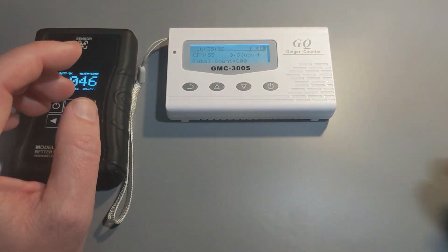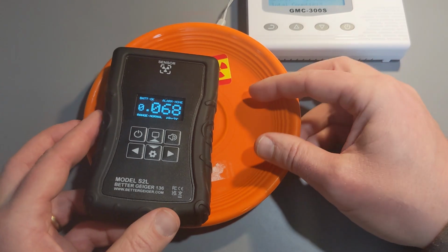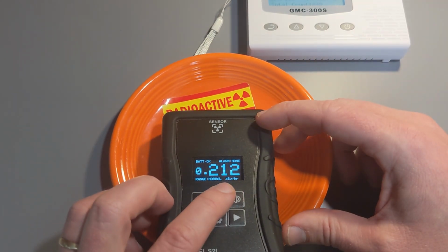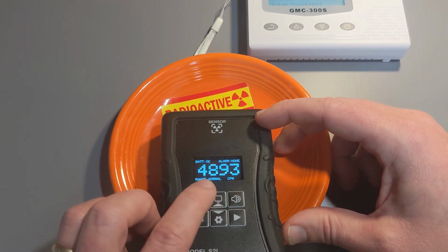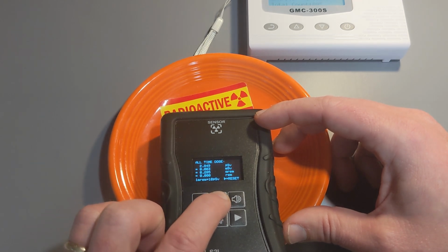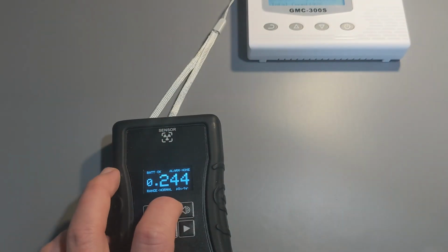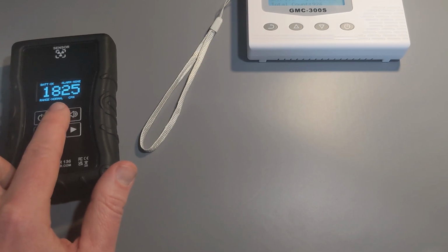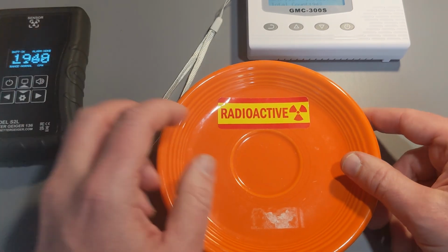And another situation where the same kind of issue comes into play, this is measuring a little bit of gamma, but mostly beta. And this is picking up some of those gammas, and the dose rate's gone up a little bit, so it's maybe doubled or so. And if we look at the count rate, it's around 5,000. If we go back to dose rate, you see it's about 0.2. If I take this away, the count rate will drop to, I don't know, maybe half of that. So generally speaking, it goes up a little bit because there are some X-ray and gamma coming off of this.